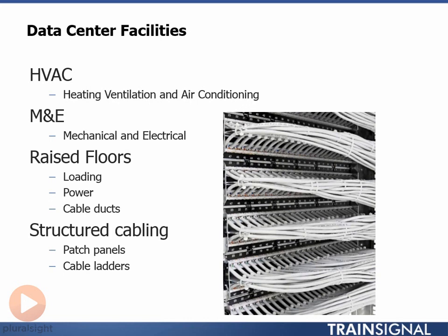Patch panels allow for tidier, easier, and safer cable management than if we were to run cables directly from servers to switches and switches to storage. For example, instead of having to put your hands in near the back of a server, switch or storage array every time you want to fiddle around with cabling, we can often do most of the work at the patch panel, lowering the risk of things like knocking out the power supply to kit.